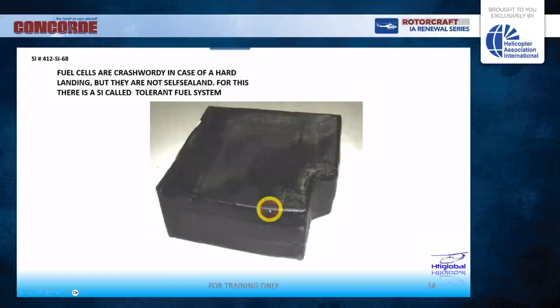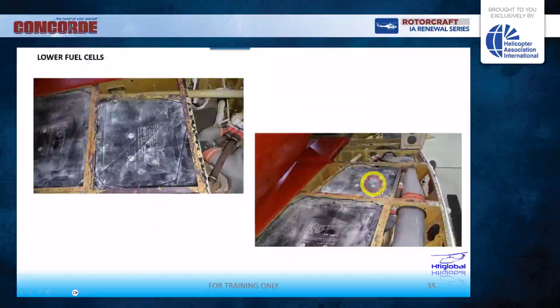All the Bell 412 bladders are crash-worthy, but they are not self-sealing. For that, the helicopter has a Service Instruction, SI 412-SI-68, called the tolerant fuel system. This one is like a two-layer design with a gel, so if you get a bullet or something that punctures the bladder, the mixture between the fuel and the gel product seals the cell and you have no leak. But it's very heavy, and it's an option the customer can choose.